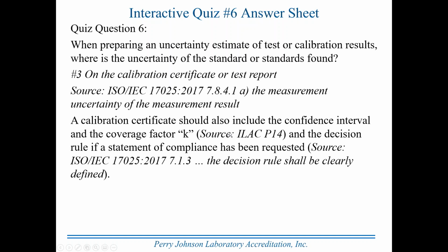Okay, a calibration certificate should also include a couple of other pieces of necessary information. It should include the confidence interval, typically 95%, and the coverage factor, typically 2. The source for that, again, is ILAC P14. We've mentioned it before, but it doesn't hurt to mention it again. And the decision rule, if a statement of compliance has been requested. That comes from 17025, 7.1.3 for the use of the decision rule.